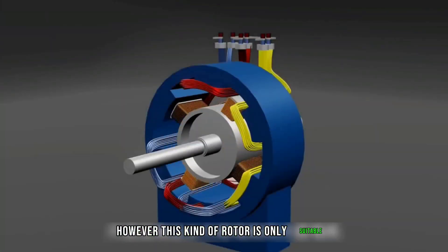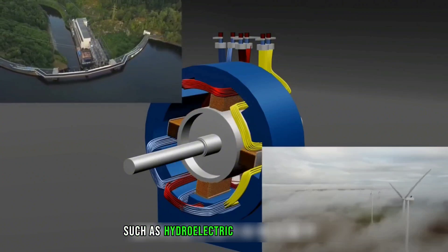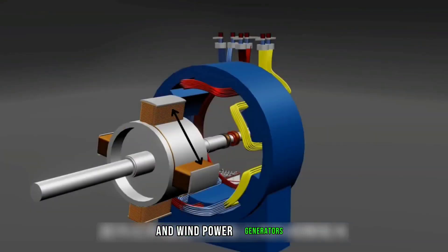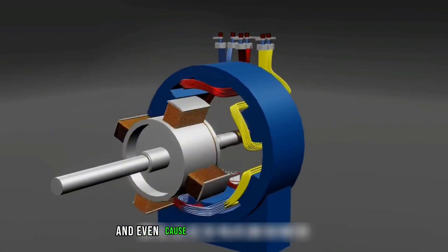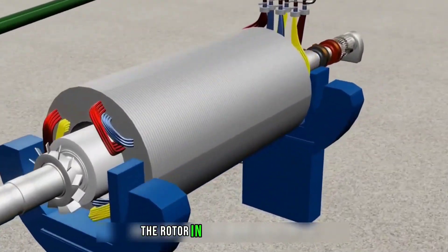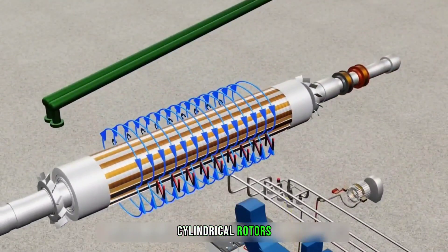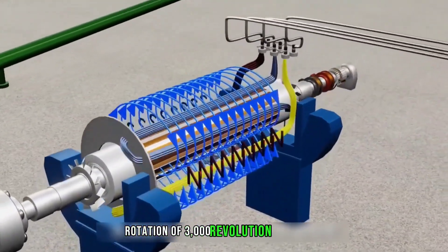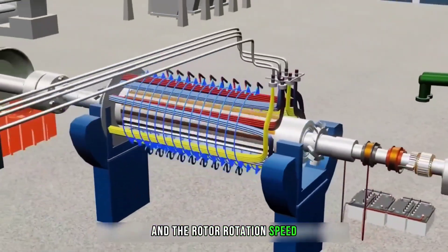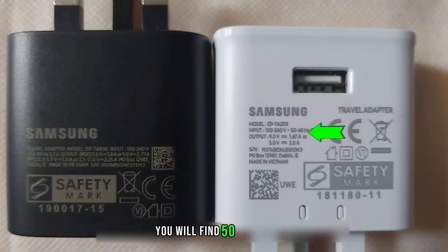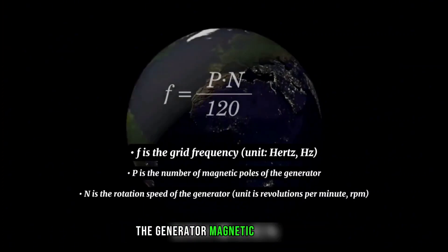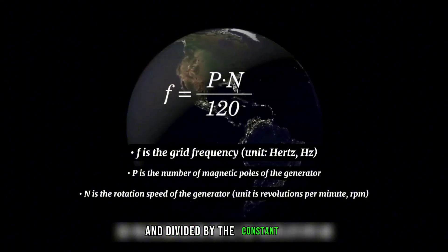However, this kind of rotor is only suitable for slow-speed power generation equipment, such as hydroelectric and wind power generators, because the gap between its magnetic poles is large and high-speed rotation will cause imbalance and even cause the generator to fall apart. For example, the rotor in a thermal generator uses a two-pole cylindrical rotor to meet the high-speed rotation of 3,000 revolutions per minute. The rotor speed determines the frequency of the power grid — you will find 50 to 60 hertz marked on many chargers. The grid frequency depends on national or regional standards, with most countries using 50 hertz. Its calculation formula is: number of generator magnetic poles multiplied by generator speed, divided by the constant 120.